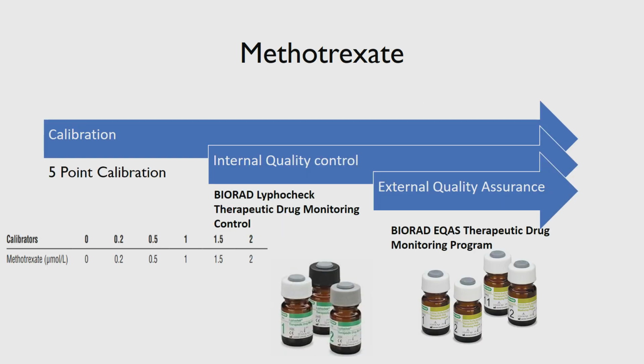So similar to anti-epileptic drugs, we need to do the calibration, the quality control, and the external quality assurance for assuring the quality of the assay. So we have a 5-point calibrator here that we use for the calibration, and similar to the anti-epileptic drug, we have a Biorad Lyphocheck therapeutic drug monitoring control for the internal quality control, and we have also enrolled in the Biorad EQAS therapeutic drug monitoring program for the external quality assurance.